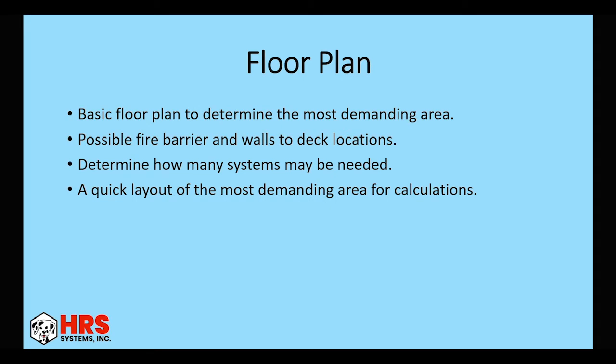So then you want a basic floor plan. A lot of times at this point in the project, I literally just have an outline of a building. So you might not have a floor plan, but it would be nice to have. Most architects when they're bringing in fire protection at this point, they've already basically laid out the occupancies. So you'll have that information to work with and you can determine the hazards and occupancies at that point and determine where your most demanding area will be. Then you're also going to want to know where possible fire barriers are or walls to deck to help with determining which area will be most demanding. How many systems you might need. This could change how your calculations are and where you run your piping. And then a quick layout of the most demanding area for calculations. So it would be best to do a quick layout, but I'm going to show you ways to get around actually laying out any sprinklers on the design or on the floor plan. So that you can just quickly go through and get an estimation in a few minutes.